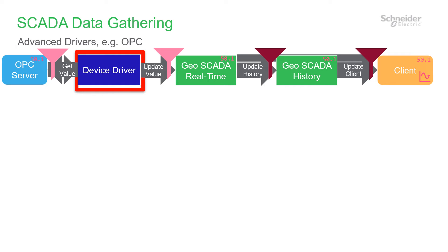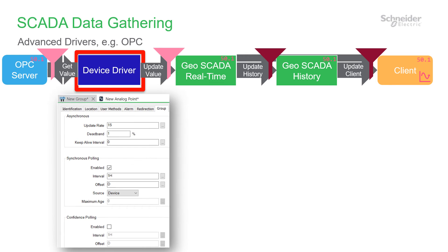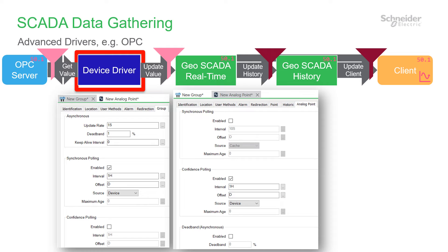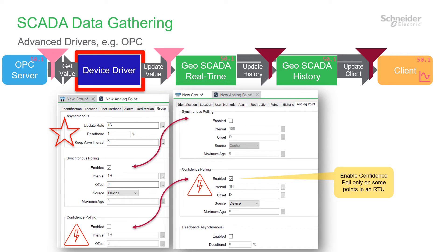For advanced drivers such as advanced Modbus, OPC, and protocols like DNP3, and for SCADAPack, there are many more features and greater diversity to allow you more flexibility. Advanced drivers provide ways to configure data reading rates by the scanner or device group, and they also enable specific options for individual points. Here you can see the advanced OPC settings for group and point, where you can set up polling on each. The objective is to filter out the noise and keep the information. For OPC, please consider using asynchronous mode to move the filtering into the OPC server. Settings for the filter are defined on the group. It's really important to recognise that confidence polling is a feature you must use sparingly — it forces data updates and storage across the system, and is only needed, if at all, for hourly or longer intervals.